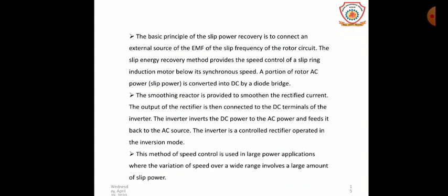The basic principle of slip power recovery is to connect an external source of EMF of the slip frequency to the rotor circuit. This method provides speed control of a slip ring induction motor below the synchronous speed. A smoothing reactor is provided to smoothen the rectified current. The output of the rectifier is connected to the DC terminal of the inverter, which inverts the DC power back to AC and feeds it to the AC source. This method is used in large power applications where wide speed variation involves large amounts of slip power.